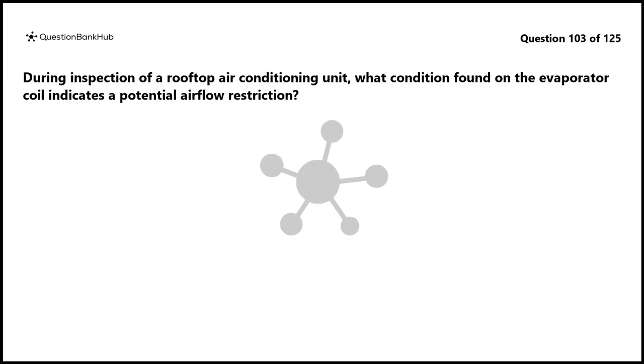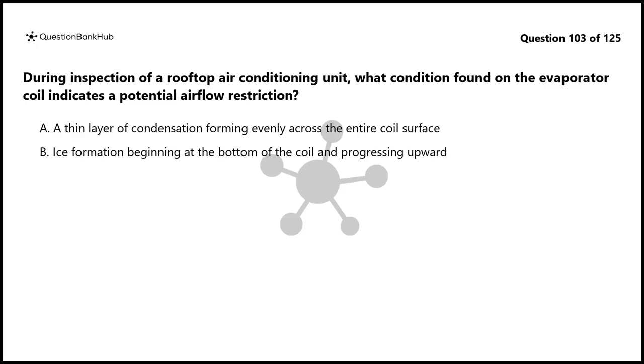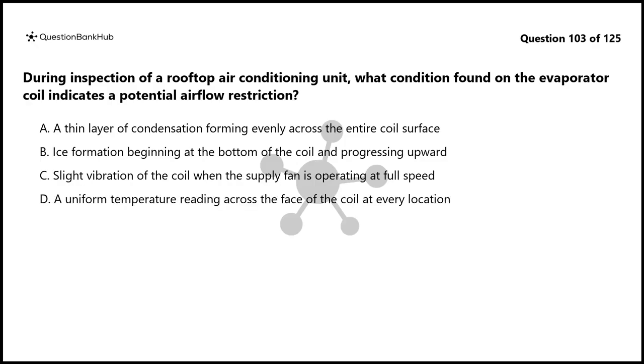Question 103. During inspection of a rooftop air conditioning unit, what condition found on the evaporator coil indicates a potential airflow restriction? A. A thin layer of condensation forming evenly across the entire coil surface. B. Ice formation beginning at the bottom of the coil and progressing upward. C. Slight vibration of the coil when the supply fan is operating at full speed. D. A uniform temperature reading across the face of the coil at every location.